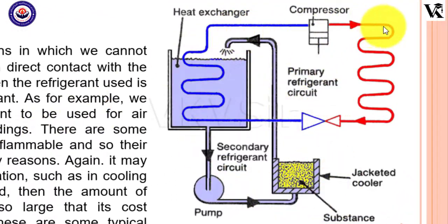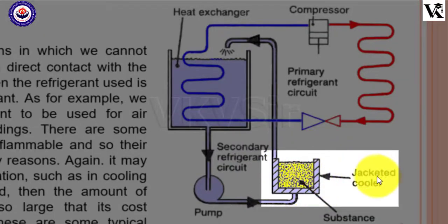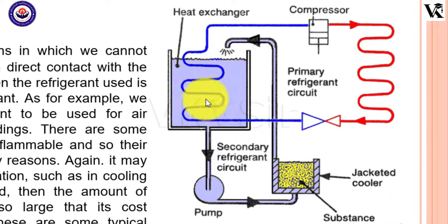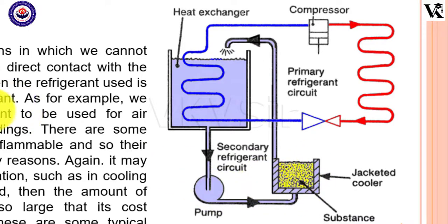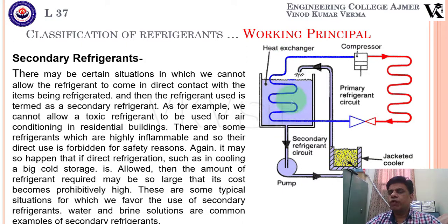So what do we do? In the primary circuit, the primary refrigerants flow and complete the cycle. If they are toxic or flammable, their direct use is forbidden for safety reasons — no poison or toxicity, no flammability in the secondary zone. We keep the toxic or flammable refrigerant in the primary circuit and take another solution like a brine solution to the secondary circuit for cooling.